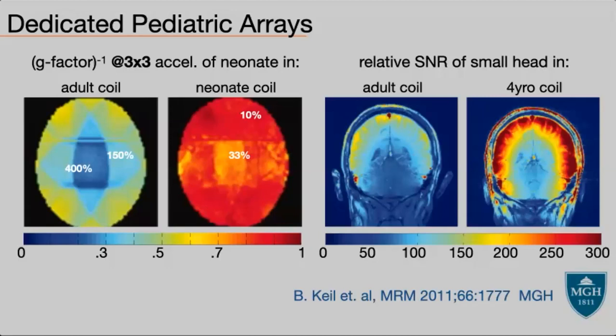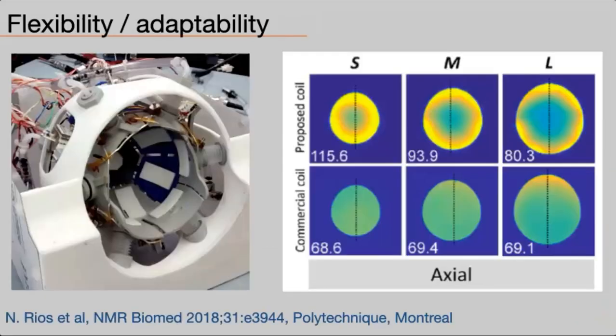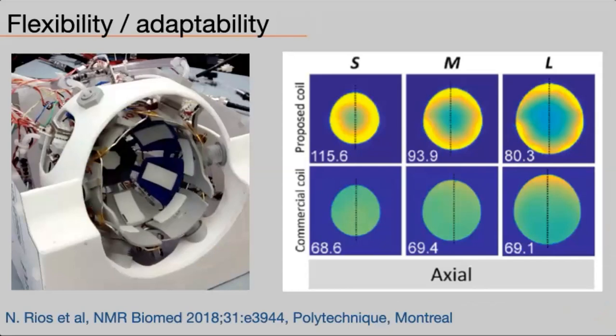While scanning the same patient in an adult coil will sometimes result in a 400% reduction in SNR. That basically makes it useless — you can't really go that far anyway. So this setup allows you to do it, and this one doesn't. Neonate in a neonate coil, that's the key. So coil size matters.